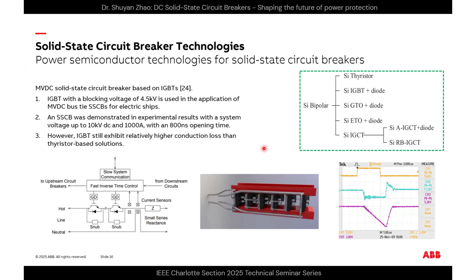That's basically because of the difference in semiconductor structure. Next are some solid state breakers based on IGCT technologies, from those works. Topology one is based on an asymmetrical IGCT with a series diode, a bidirectional topology. Topology two uses anti-series reverse conducting IGCTs to still form a bidirectional solid state breaker main topology. And the reverse blocking IGCT, called RB-IGCT, is typically accomplished by integrating a blocking diode and IGCT on the same die of the semiconductor, for a substantial reduction of power losses of this topology.